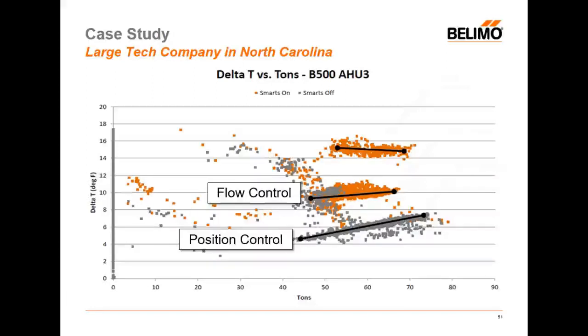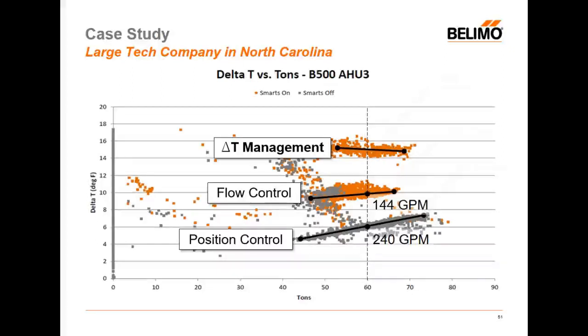Then we use flow control, that's the next level. And then we use delta T management. And if we use these three modes, what we can see is we still need 60 tons of cooling. But in position control, we're going to need 240 gallons of water a minute. That's because of inherent waste. In flow control, because I'm limiting the saturation at the time it's happening, I'm not waiting for the thermostat, I only need 144 gallons of water.